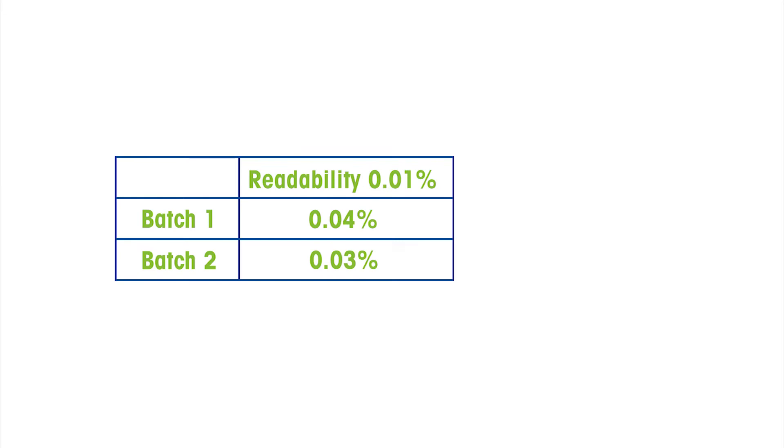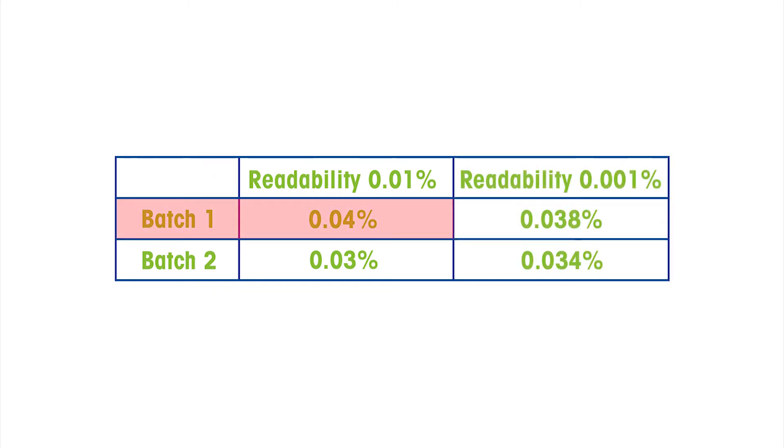In this example, a moisture content of 0.04 percent and above is out of specification. With 0.01 percent readability, the first batch would be discarded. With the higher readability, we see that both batches are within specification.